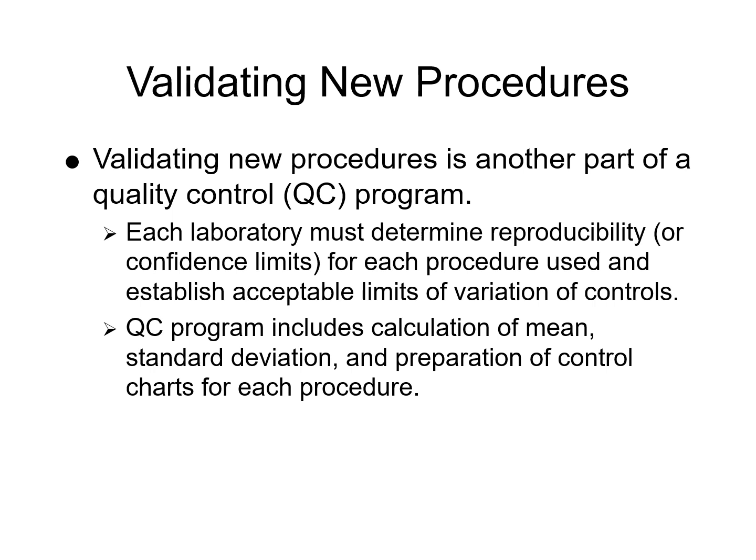Quality control program components: we're going to have the calculation of the mean, which will determine the central tendency of those control results. Standard deviation is going to measure the variability of repeated measurements. And then our control charts are a graphical representation of control results over time, which will detect trends or shifts in assay performance. It will help to identify potential errors early and ensure results remain within acceptable limits. So validation and ongoing QC are critical for maintaining accuracy, precision, and reliability of laboratory testing. Calculating mean, standard deviation, and maintaining control charts are a pretty fundamental QC practice that all laboratories take part in.